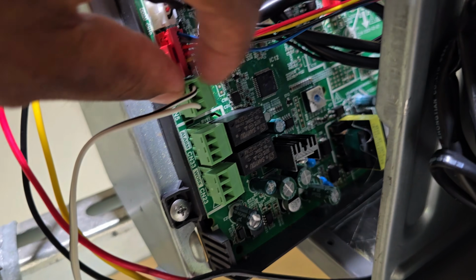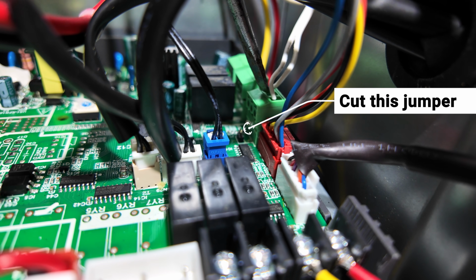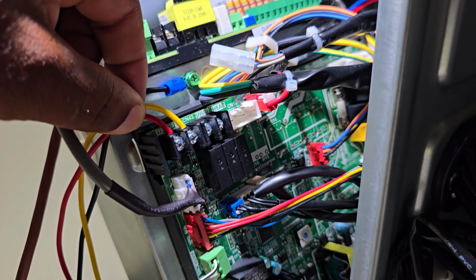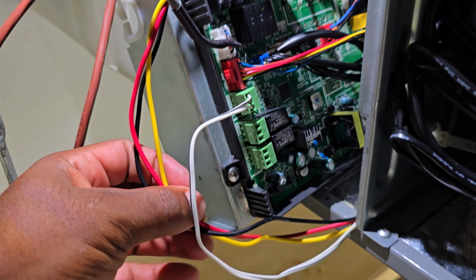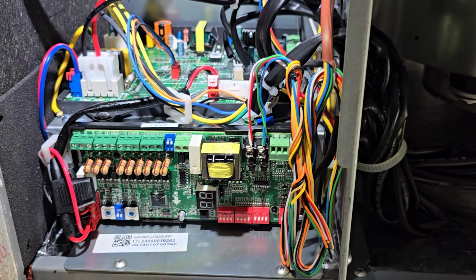This is where the water switch will go. Since I will have a float switch connected to the terminal, right beside the block there's a little jumper that's hidden, and that needs to be cut. Right on the top board, this is where I connect the S1 and S2 communication to the outdoor unit.